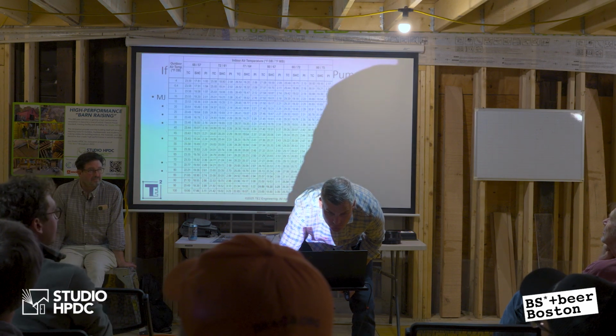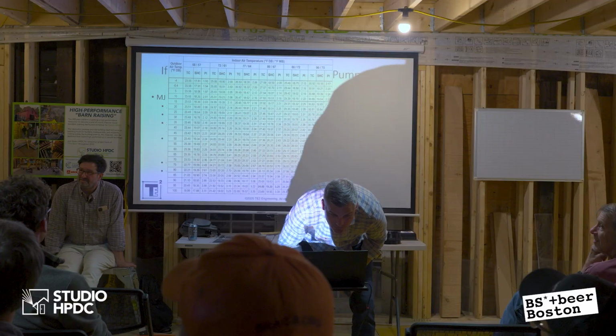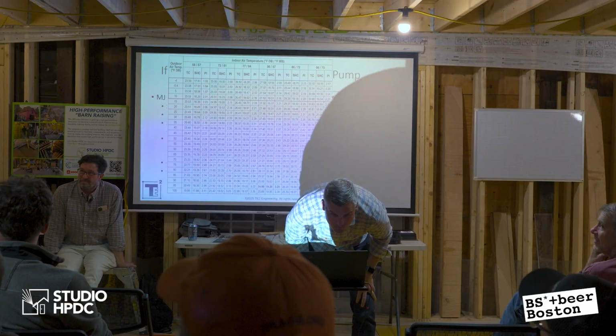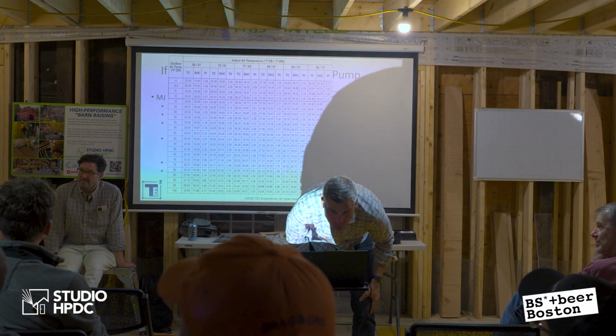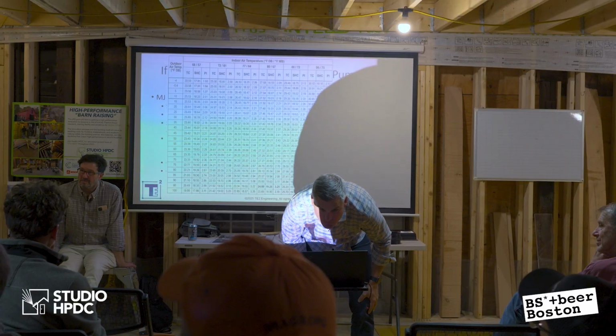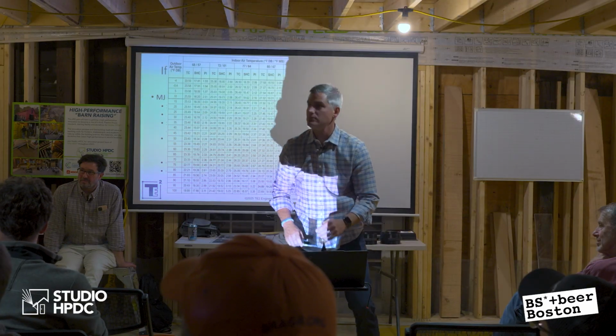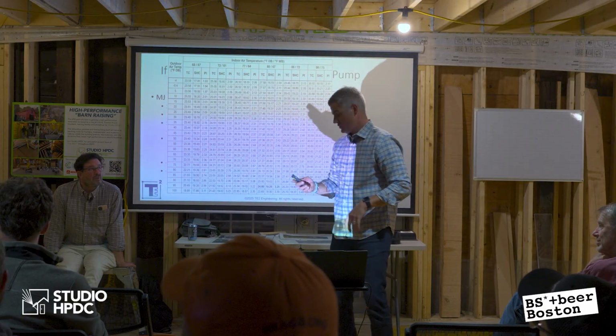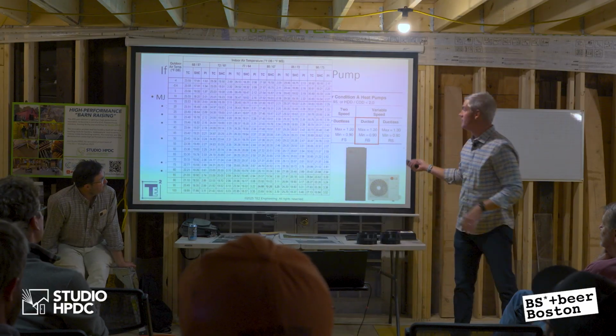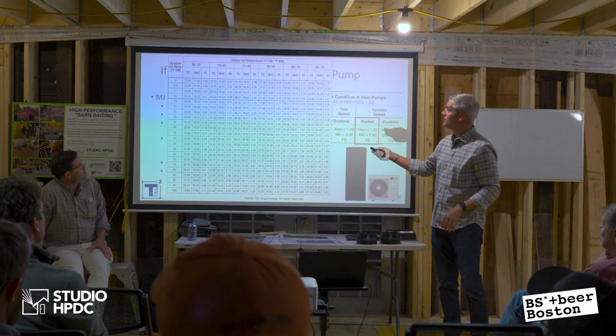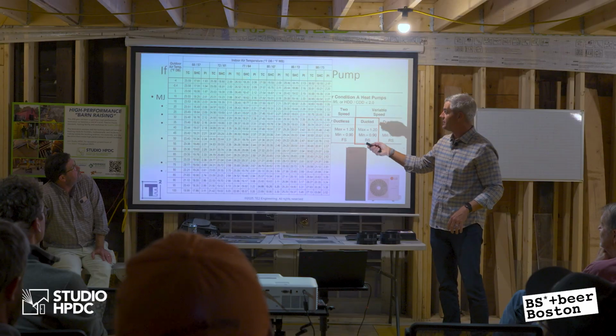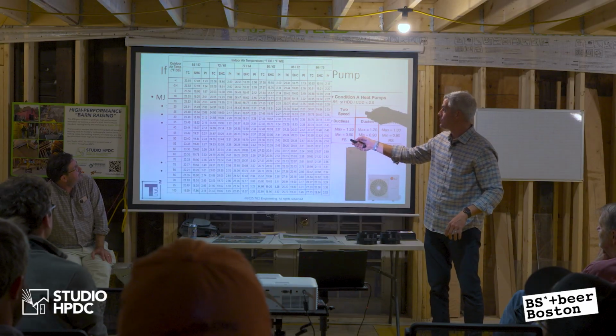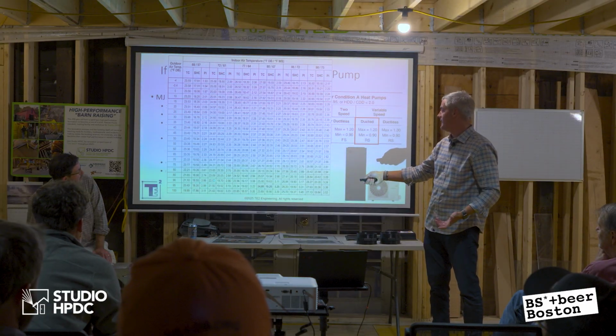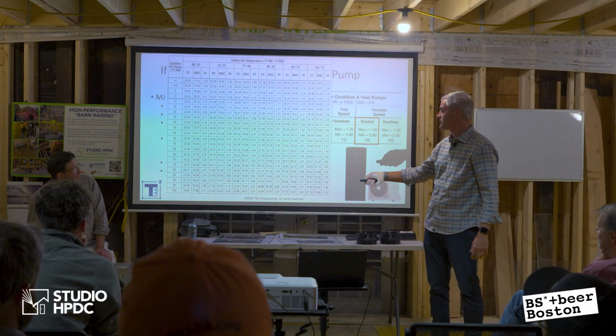So in my personal house, on a call for dehumidification, I keep my coil at 44 degrees. I run about 260 CFM through my house, which isn't enough to actually cool it, but it does dehumidify quite well. So if I look at a Mitsubishi unit, I look at its performance chart. If I look at most of the operating conditions, I look at sensible heat capacity and total capacity. If I look at, let's say, 90 or 95 degrees, you see how close these numbers are?